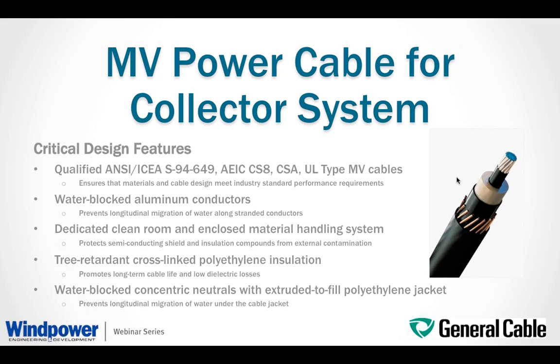Then, as Brandon was also talking about, when it comes to the conductivity versus the economics of aluminum versus copper conductor, aluminum is really the primary material being used for underground residential distribution cables by the utility, because it makes the most sense as far as cost of the metal versus the conductivity of the metal. Utilities will use copper conductors in an area where they require either higher ampacities or the cable will be installed in conduits, and then you're limited by the dimension. For the buried application in the wind farm, aluminum conductors are typically what make the most sense in the collector system.